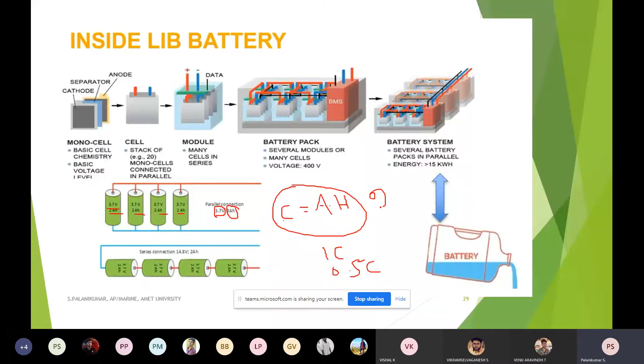So the way we have to understand the ampere hour is like that only. At discharging voltage, what is an ampere hour? If you take it as a C value, I can go for 2C, 1C, and 0.8C. So based on the method we are discharging the battery, the lifetime of the battery will be affected. Usually, what is suggested is we have to go for fractional rating of charging only. So I can go for 0.8C, I can go for 0.4C. Automatically, that leads to more battery life.